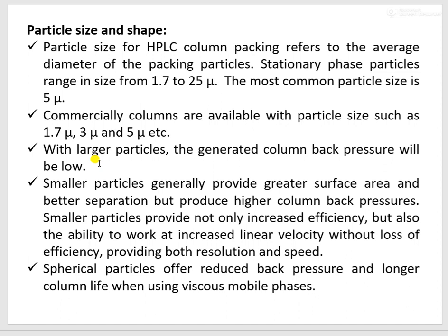Large particles cannot form a compact mass, and hence the back pressure associated with larger particles will be less. Smaller particles generally provide greater surface area and better separation but produce high column back pressure. Smaller particles provide not only increased efficiency but also the ability to work at increased linear velocity without loss of efficiency, providing both resolution and speed. With a small particle size stationary phase, the number of theoretical plates will be high and resolution will also be very good.